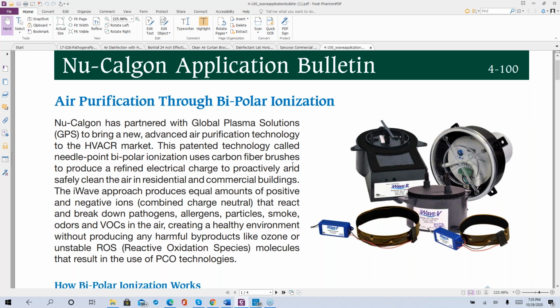everything that they can bond to and make inert. And when all are attached together with the like-charged molecules, they become large enough to be captured by a standard MERV 8 or the recommended MERV 13 filters that nobody can buy because they are the same filtration media that's used in the N95 masks. So that's the reason why there's such a short supply. So you don't really need the HEPAs anymore. And the HEPAs you really couldn't put in a standard system anyways because of the static. So this gives you that ability to disinfect, clean, as well as filter without going the route of HEPA.